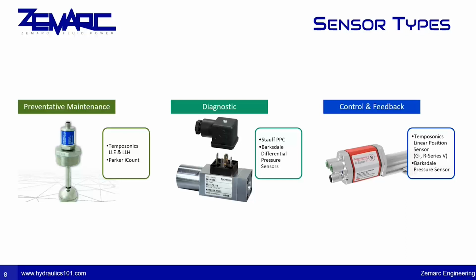So the Stauff PPC gives feedback on contamination levels, fluid temperature, and pressure. Then we have things like the Barksdale differential pressure sensor, which is designed to measure the difference in pressure between 2 points. Or you have control and feedback sensors, which aid in controlling a system. These often include temperature, pressure, and position sensors, like the Temposonics R Series 5 linear sensors, which measure the position of an object, such as a cylinder. And last, Barksdale pressure sensors, which measure the pressure of a fluid or gas in a system.